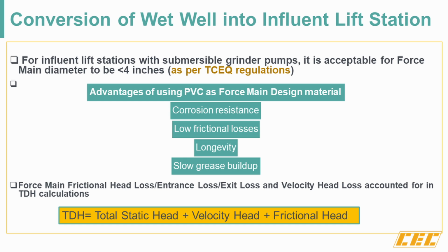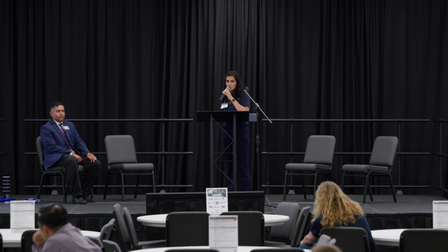And to determine the total dynamic head, which I talked about, that is to overcome the pressure, the primary calculation that was used is here. So the total dynamic head would account for the total static head, velocity head, and frictional head. These were the factors that were used in determining the total dynamic head.